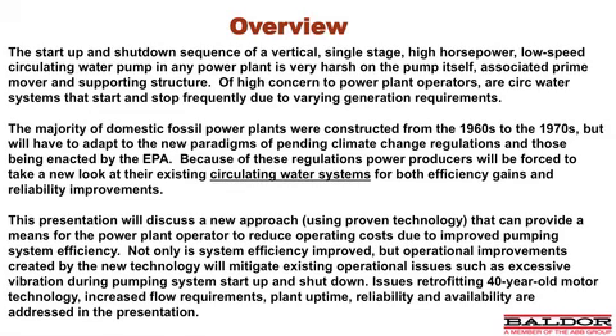The startup and shutdown sequence of a vertical, single-stage, high-horsepower, low-speed circulating water pump in any power plant, be it coal or combined cycle, is very harsh on the pump itself, as well as the associated prime movers and supporting structure. Most power plant operators have a tendency to start and stop the circ water system frequently and cycle the power plant. This is most prevalent in combined cycle pumping applications.